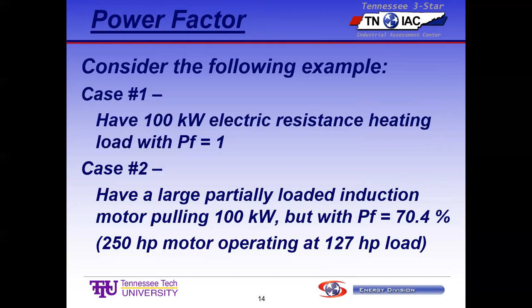Case one: there is no reactive power, so the power triangle collapses to just two lines. This is the kW and the kVA, and they're both 100, laying right on top of each other. Pretty simple. Two straight lines on top of each other. So let's do the math. I made up a voltage; let's say the voltage is 230. Let it be whatever you want, just keep it constant. So 100 kW, 230 volts, and I went ahead and calculated the amps. This requires 251.3 amps, power factor 1.